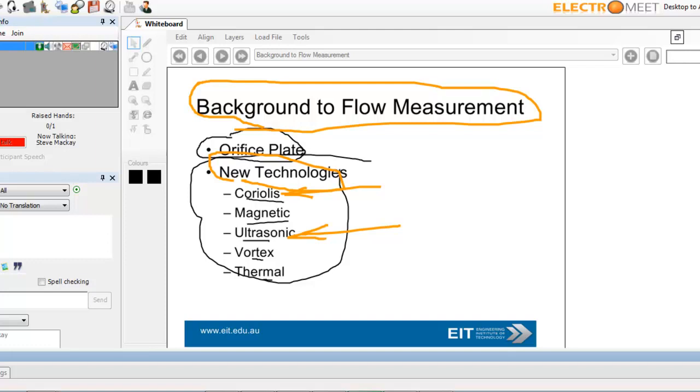The other one, which is always fascinating, is the good old magnetic flow meter. Here, use wire coils on outside of the pipe, two coils. You put a voltage to the coils, generate a magnetic field. And the magnetic field impacts on the conductive liquid going through the pipe. And you have two more probes, which detect the voltage across those electrodes on either side of the pipe. And that voltage, you will then work out the flow rate.